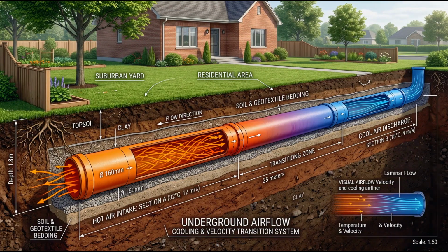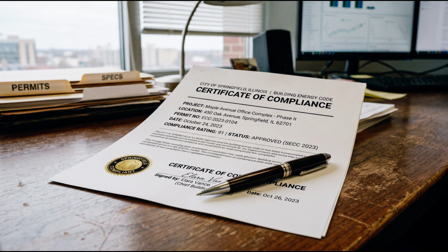At the house itself, route the pipe through a wall penetration or an existing basement window well, bringing it cleanly into the building envelope. Seal that penetration point properly using a rubber sleeve and expanding foam to keep the whole system airtight and pest-free. On the permit question, most local jurisdictions don't require a formal permit for digging in your own yard as long as you're not touching or altering the structural foundation of the house itself. But check your specific local codes and building department directly to be sure, since these rules genuinely do vary quite a bit by location, and it's a 5-minute phone call that saves potential headaches later.